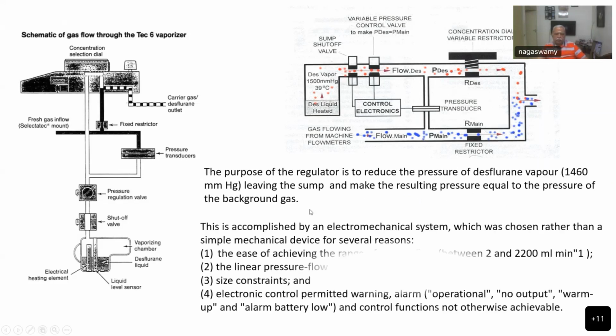And this is accomplished by an electromechanical system. It was chosen rather than a simple mechanical device for several reasons. One, the ease of achieving the range of vapor, that is between 2 and 2200 ml per minute, and the linear pressure flow characteristics, the size constraints, and the electronic control permitted warning alarms, that is operational, no output, warm up, alarm, battery low. All these things can be activated only based on the electromechanical system that is there. If it is a purely mechanical device, these control alarms cannot function.